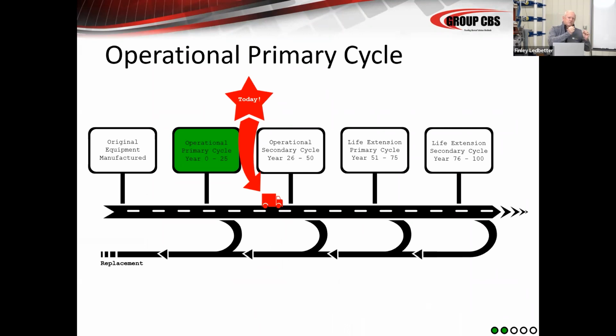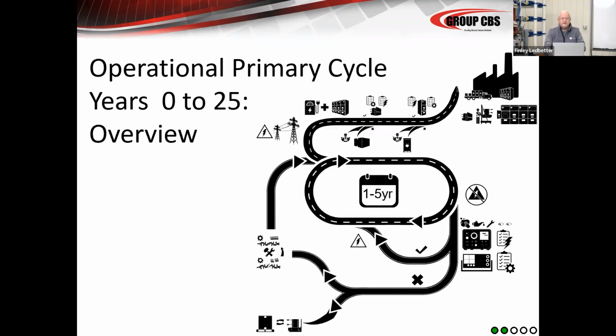What are those tests? What are those inspections? There again, that's the next segment. But let's just say that you have a maintenance program that you adhere to for acceptance testing this new gear. You have some sort of person, a third party or the original manufacturer or Joe down in QA. You've got somebody that's going to inspect this gear. This looks complicated, doesn't it? This is actually the primary life cycle path for your switchgear and your circuit breakers. And we're going to break this down into sections to make it easier to understand.